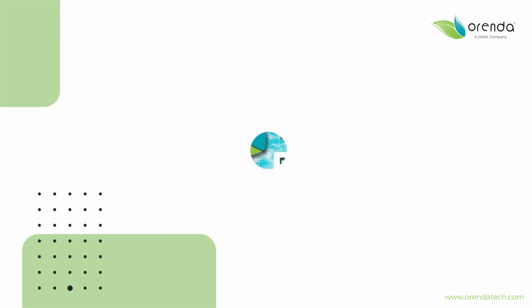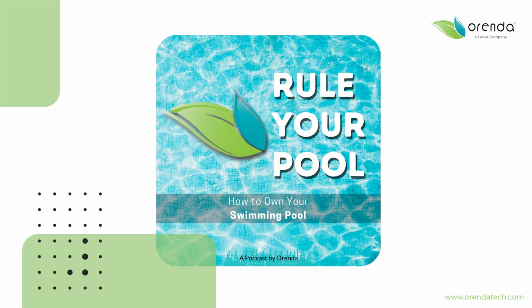I made mention in the last episode about black flakes in a saltwater pool. No, they were not calcium flakes. They were actually copper oxide. They were technically very dark green, but they looked so dark they looked like black flakes. Come to find out, it was not properly bonded, and there was a stray current between the salt cell, which was downstream, but the electrical current was going backwards against the flow of water to the heat exchanger, because that was the nearest anode that it could pull electrons from, and it did. And then it would corrode that heat exchanger to a point where it started flaking off.